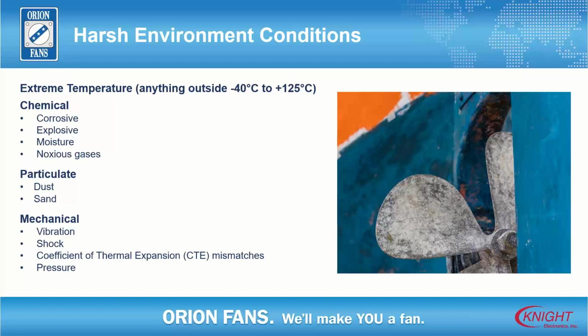Corrosive agents. These days we're seeing a lot of people using ozone for sterilization, for cleaning air, for drying organics. We'll use that term. People are pumping ozone into things. Ozone is very corrosive. It'll kill a fan in about a week, depending on the concentration of the ozone. So we have a coating that can protect the fan from the ozone.